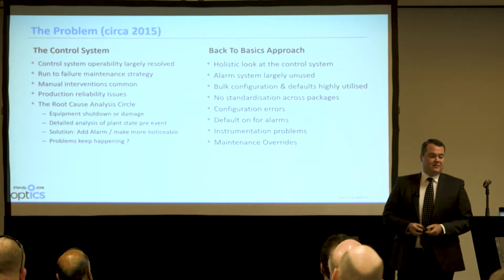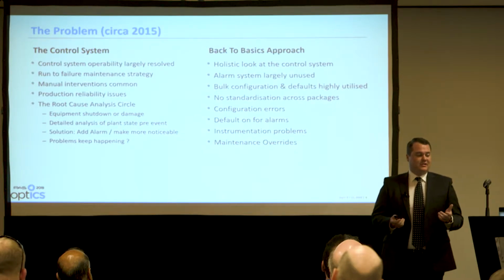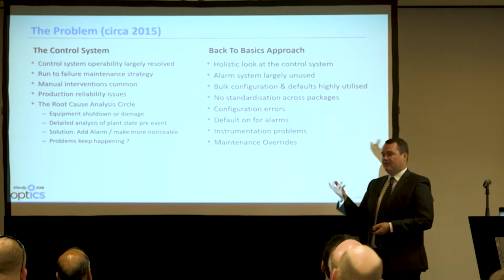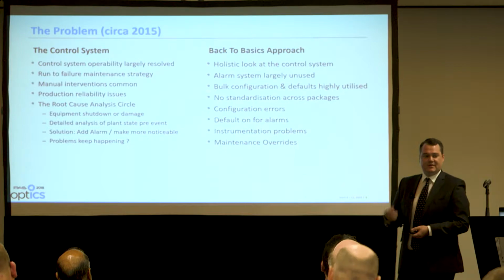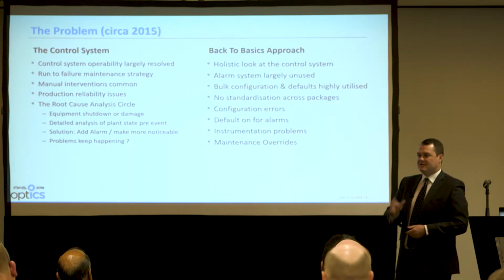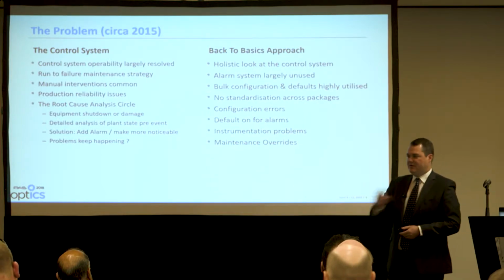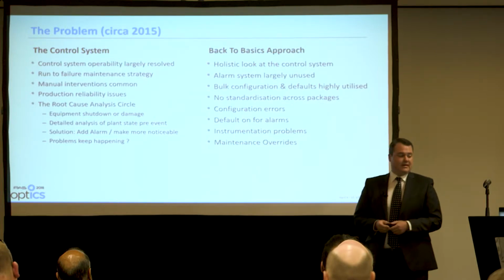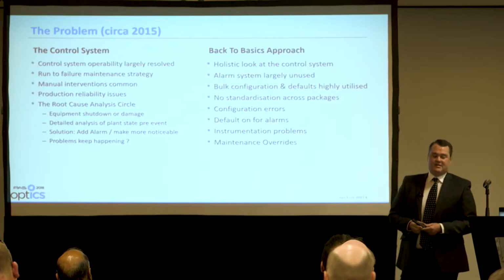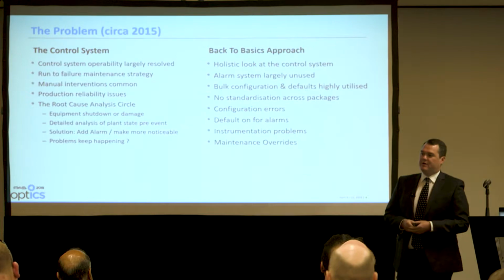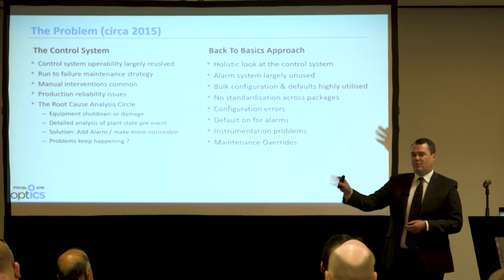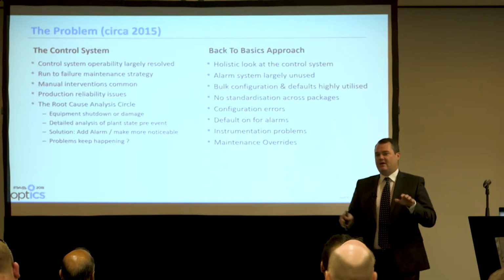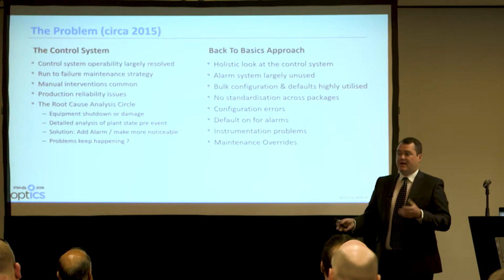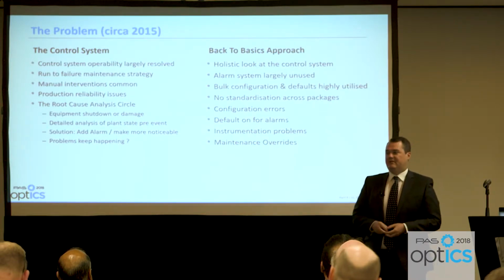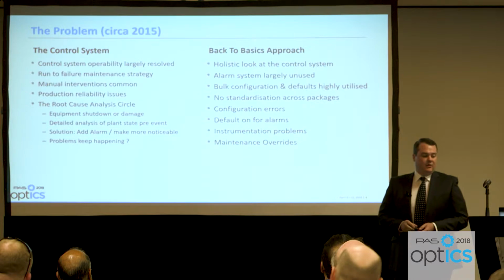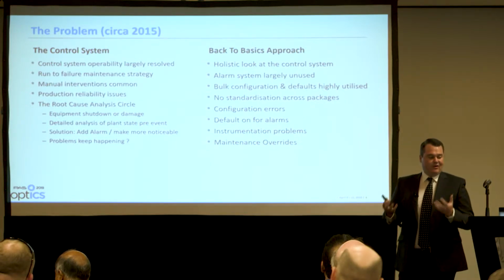We found a lot of bulk configuration, with defaults highly utilised. We've got a lot of repetitiveness in our plants - 72 odd float cells that are exactly the same, so you configure once and copy and paste, which led to a lot of errors. There was no standardisation across packages either. That big package equipment I mentioned - one comes from one vendor, one from another - and the way they do alarms, the priorities, how many come in, are all completely different. So we had a lot of configuration errors and a lot of alarms left on by default.